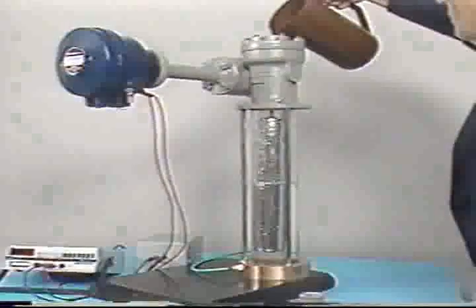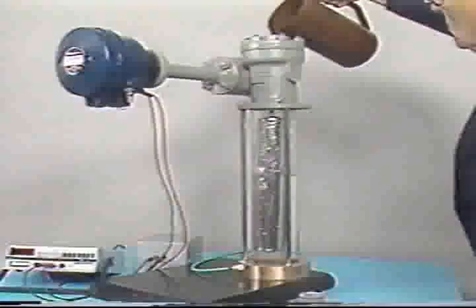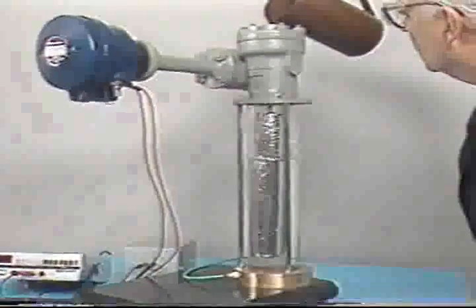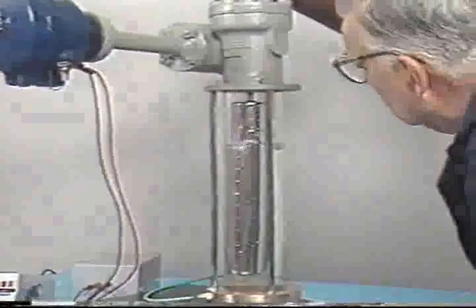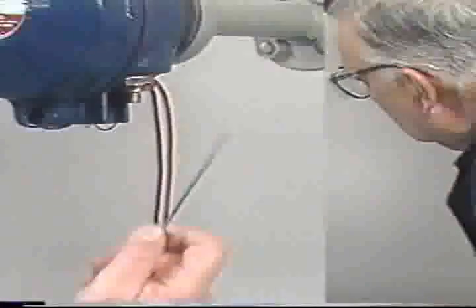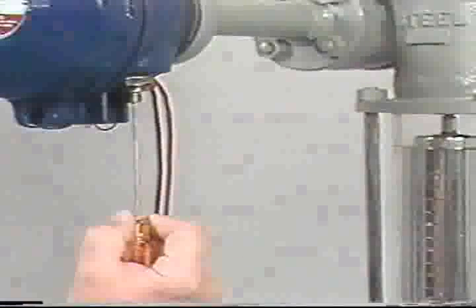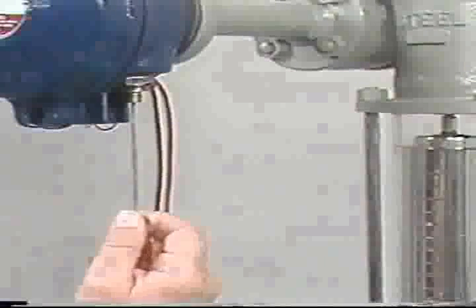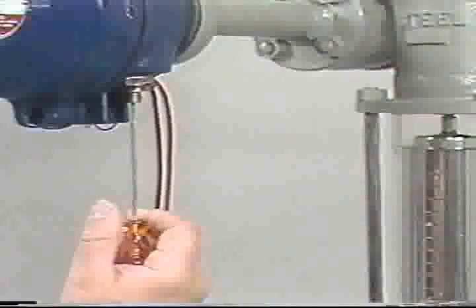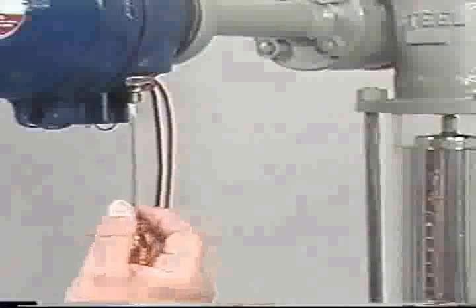The next step is to adjust the span. Fill the chamber to the upper range value. For this input, the ideal output is 20 milliamps. With the chamber full, turn the span adjustment until 20 milliamps is produced. Drain, then recheck the zero output value.